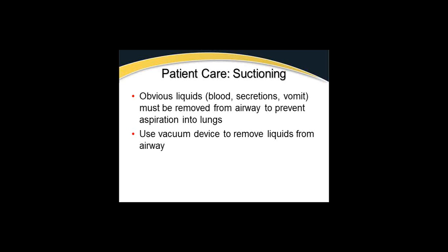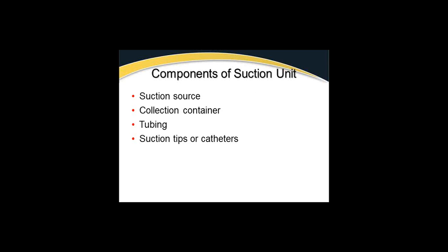If we look at 189, we have a couple of different portable style suction devices. Those are obviously going to be used in the house, in the field, you know, for someone laying on the driveway or the sidewalk or whatever. These are mobile. The one that's mounted in the ambulance is not going anywhere else. Its suction power is not coming from what you see here. It's coming remotely from a suction compressor that's behind the wall.